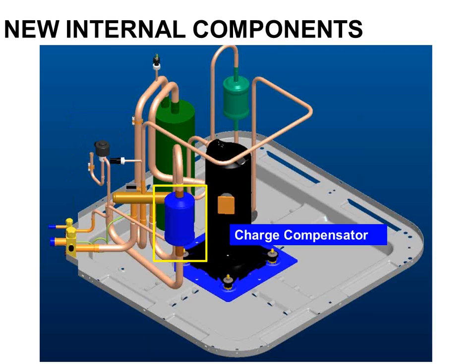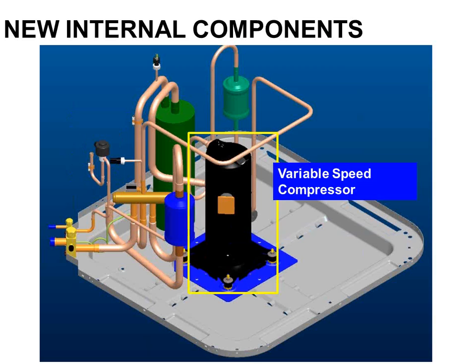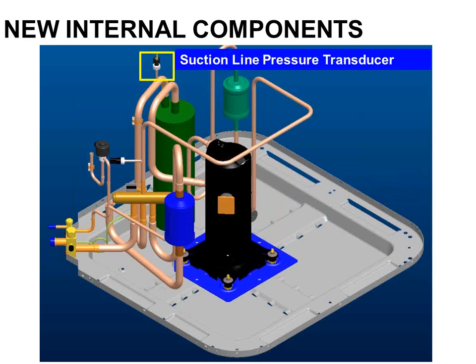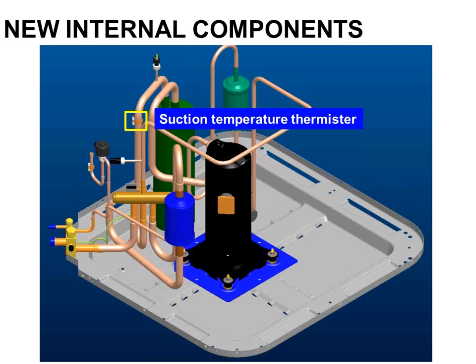I have a charge compensator. For the most part, just think of that as a buffering system to store a little bit of refrigerant when I switch from heating to cooling modes. I got a variable speed compressor, like we talked about. I got a pressure transducer on the suction line, and I got a temperature sensor on the suction line.